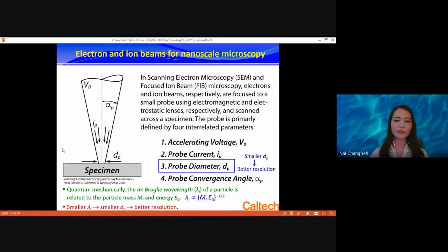So finally you have this probe. Electrons or ions come in and are focused onto this probe, which then hits your sample. The result is sensitive to the voltage you apply, the current of the particles, the angle and how you focus it, and the probe diameter. You want this probe diameter to be as small as possible for better resolution.